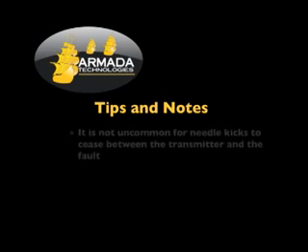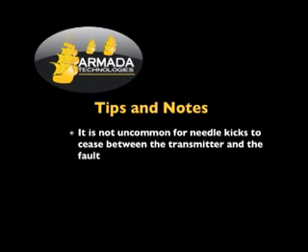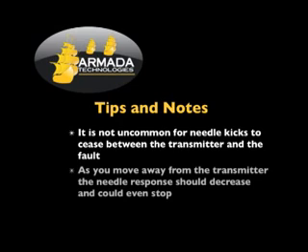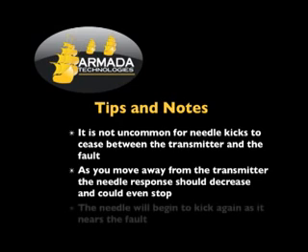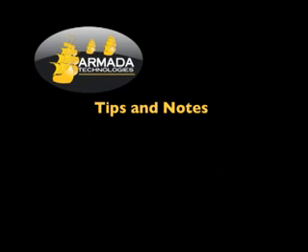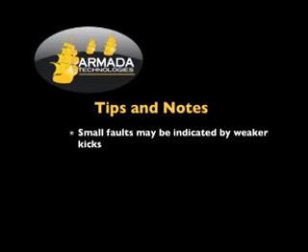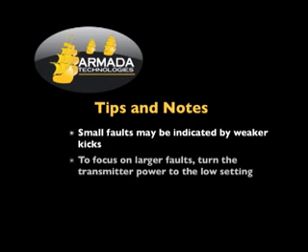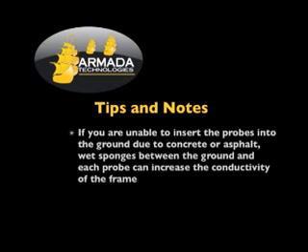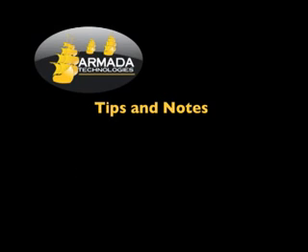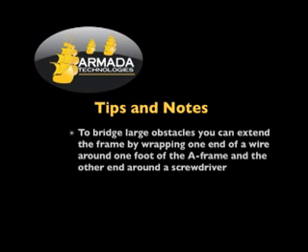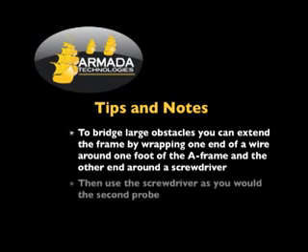It is not uncommon for needle kicks to cease between the transmitter and the fault. As you move away from the transmitter, the needle response should decrease and could eventually stop. The needle will begin to kick again as it nears the fault. Small faults may be indicated by weaker kicks. To focus on larger faults, turn the transmitter power to the low setting. If you are unable to insert the probes into the ground due to concrete or asphalt, wet sponges between the ground and each probe can increase the conductivity of the frame. To bridge large obstacles, you can extend the frame by wrapping one end of wire around one foot of the A-frame and the other end around the screwdriver. Then use the screwdriver as you would the second probe.